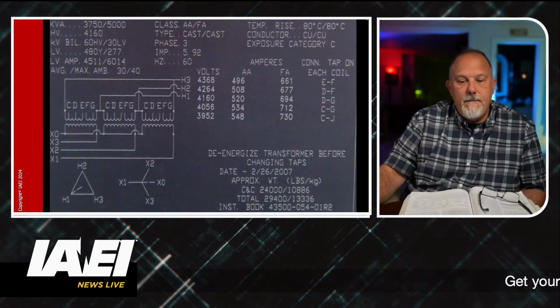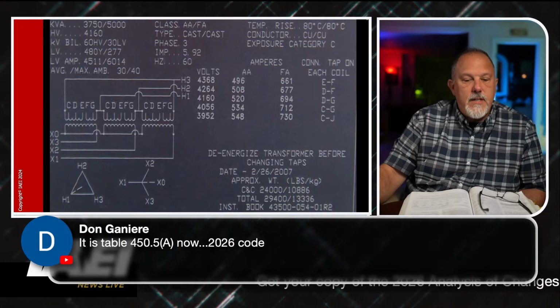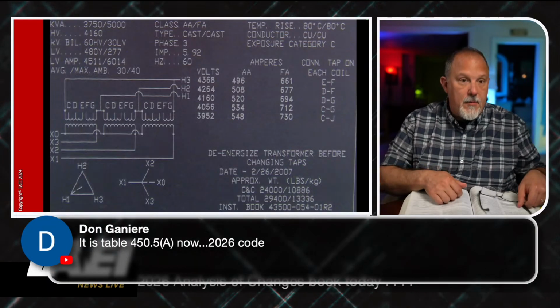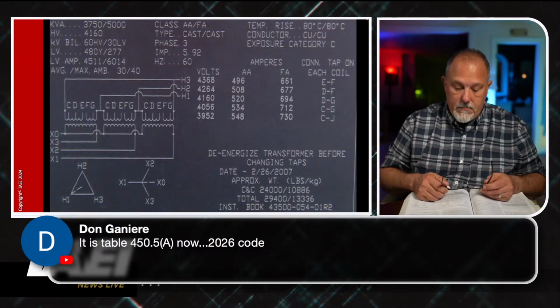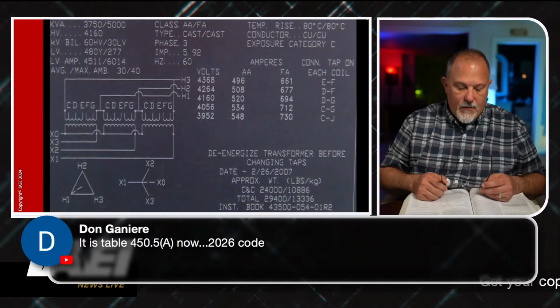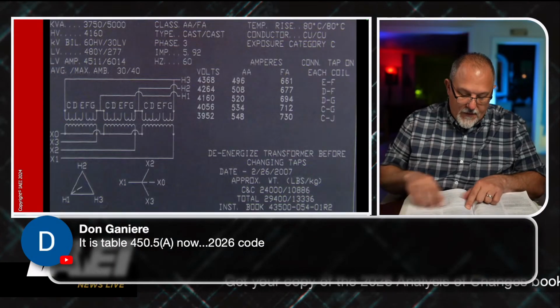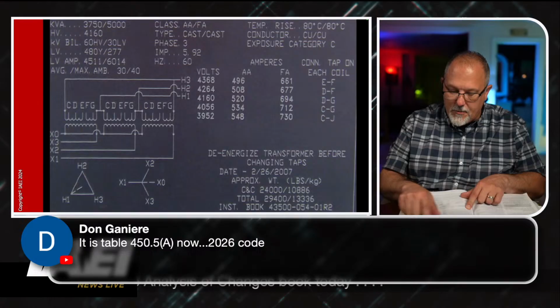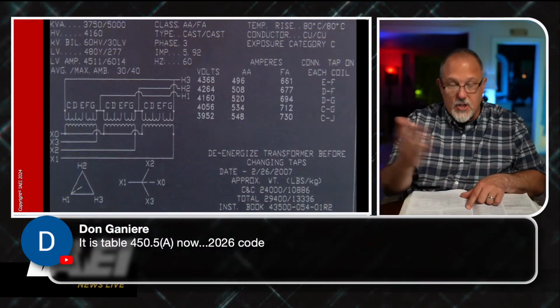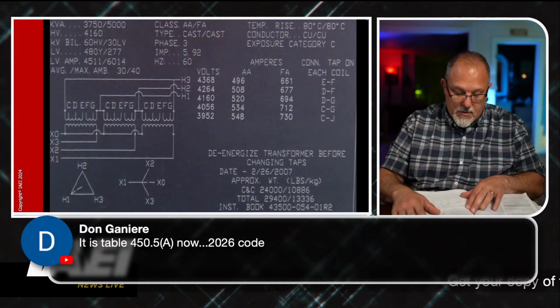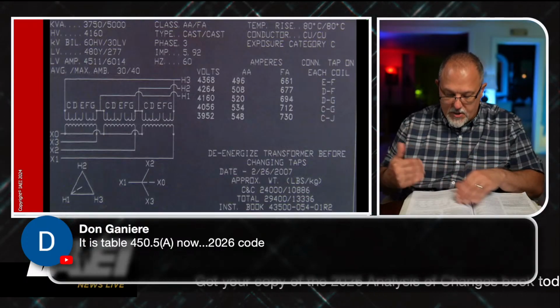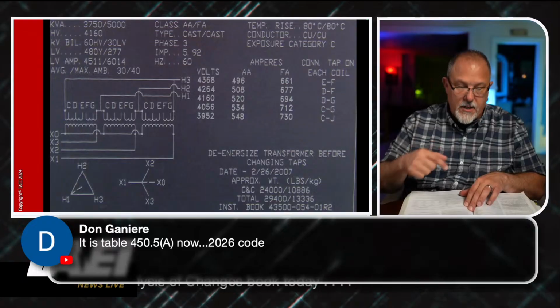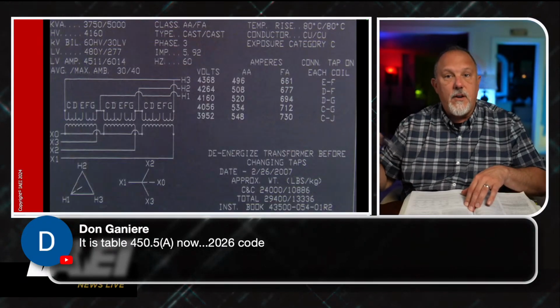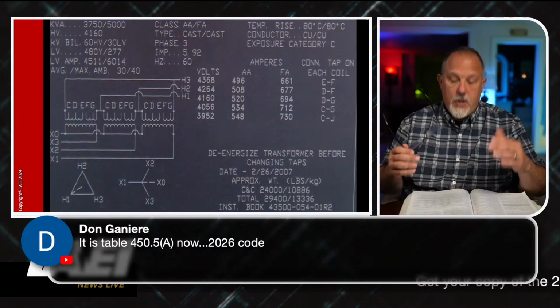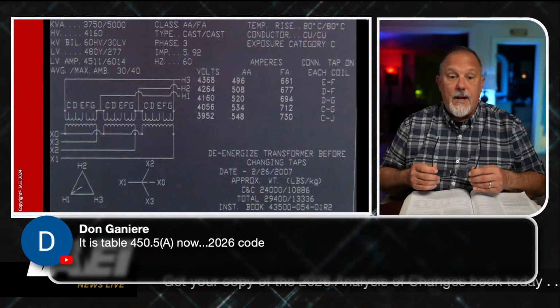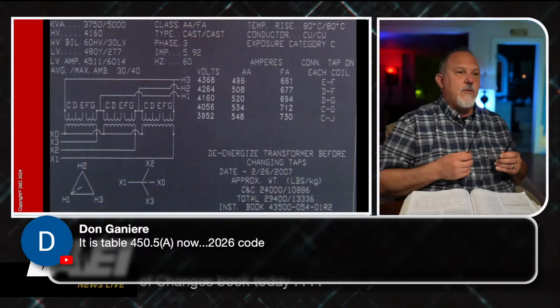so Dawn Ganir is saying that they moved the table to 450.5a. And you know why probably, Dawn? It's probably because 450.2 is the interconnection of transformers, and 450.3 is overcurrent protection. And 450.1 is scope, which it should be, but .2 and .3 are reserved now, so we probably moved everything up by 2, which means table 450.3 is now 450.5 because 450.2 is listing requirements, 450.3 is reconditioning requirements, so everything bumped up by 2. Wow. That's going to throw everybody's documents off helter-skelter.